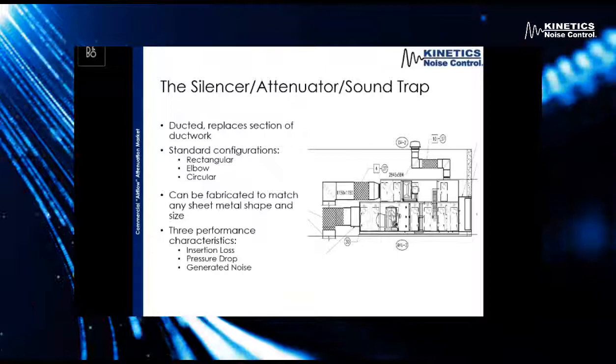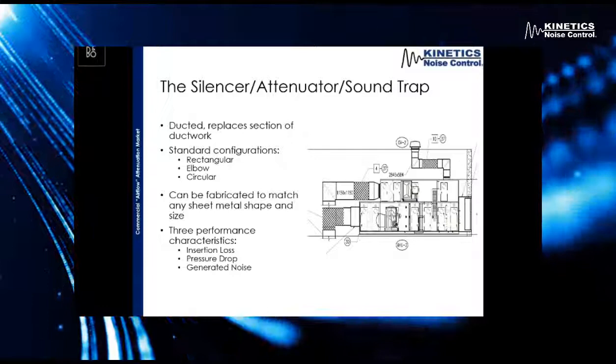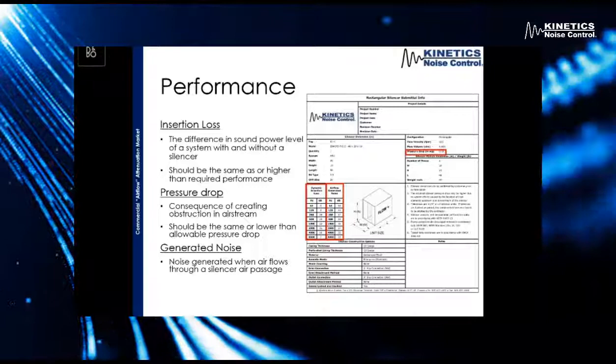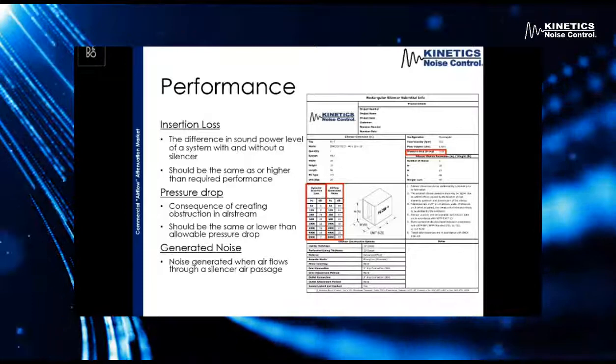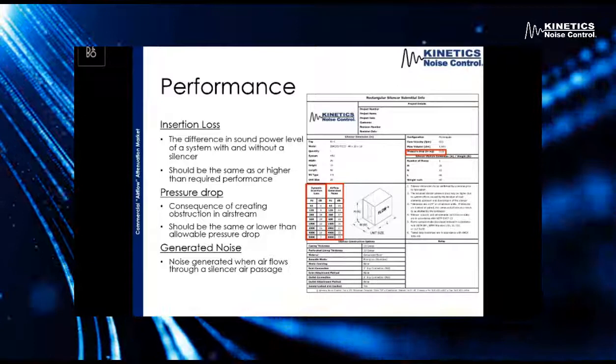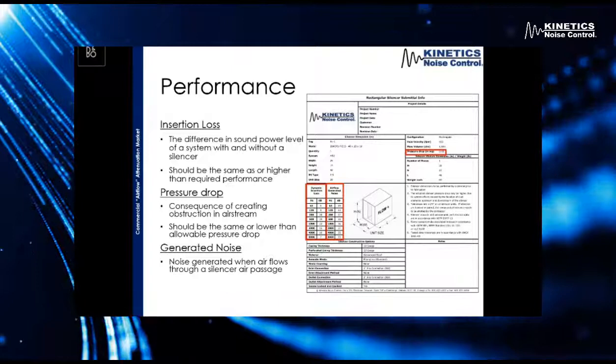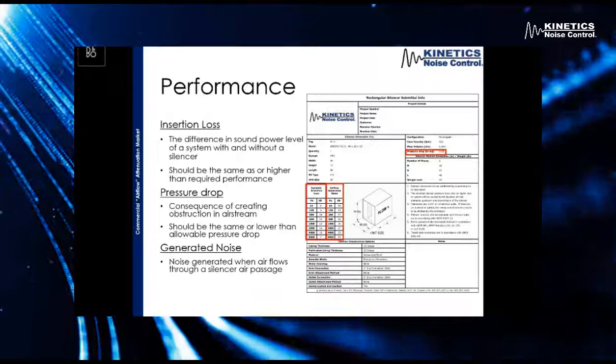The performance of the silencer is characterized in three ways: insertion loss, pressure drop, and generated noise. When I talk about the acoustic performance, I'm talking about the insertion loss of a silencer — this is the difference in sound power levels in a system with and without a silencer. On the right of the screen you can see a standard Kinetics submittal. About halfway down there's a red box that says dynamic insertion loss. You can see eight different frequencies — we work from 63 up to 8,000 Hz — and at each frequency we have an insertion loss number. This is the amount of sound energy at that frequency that's being taken out by the silencer.